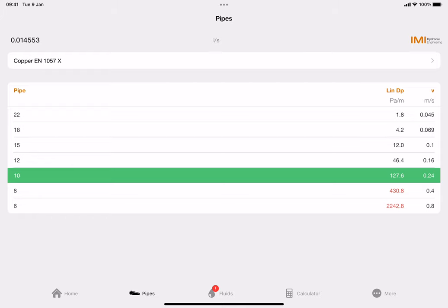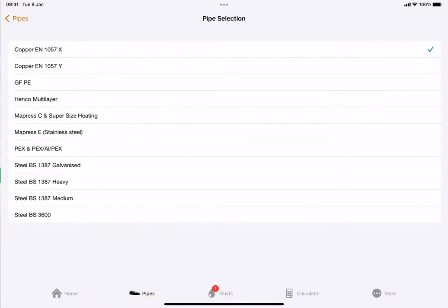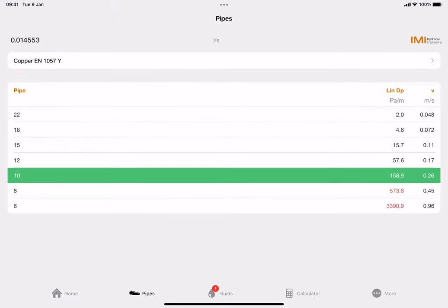You can see what it's saying: to carry 600 watts at Delta T 10 through pipe work, it states that 10 millimeter table X copper is going to be correct. Now 10 millimeter table X copper - can we get that in the UK? It's more likely going to be table Y, so I would change that to table Y. Our target linear pressure drop as we set in settings was 300 pascals per meter and our velocity within the pipe work we wanted around 1 meter per second. We've got 10 millimeter copper giving us 158.9 pascals per meter pressure drop but only a velocity of 0.26 meters per second - a very low velocity for carrying 600 watts through to that room.